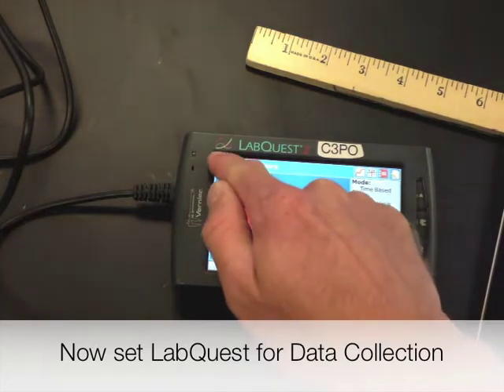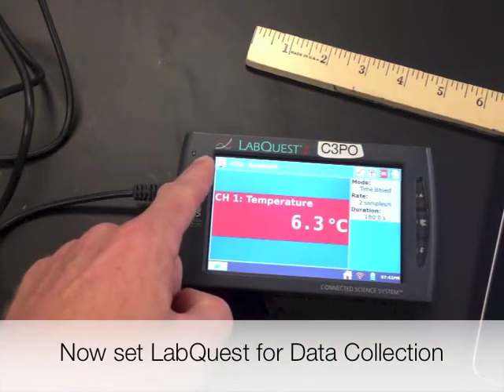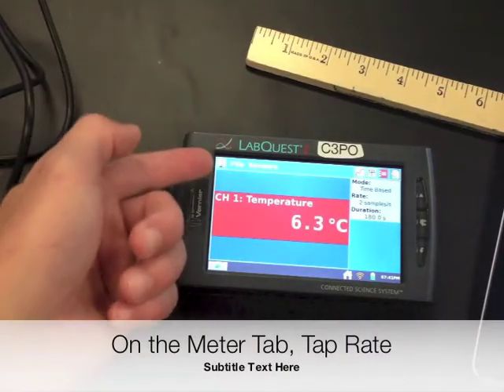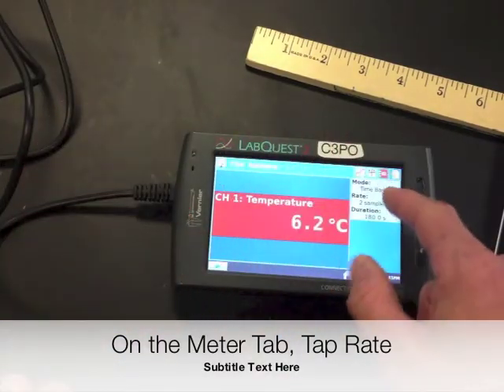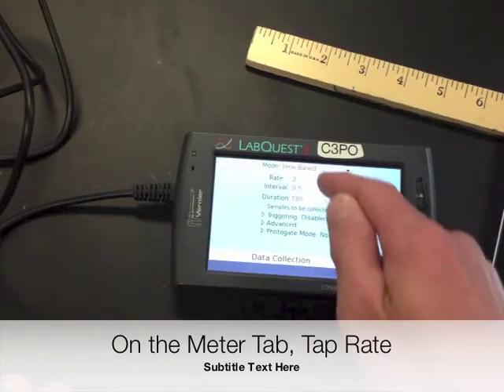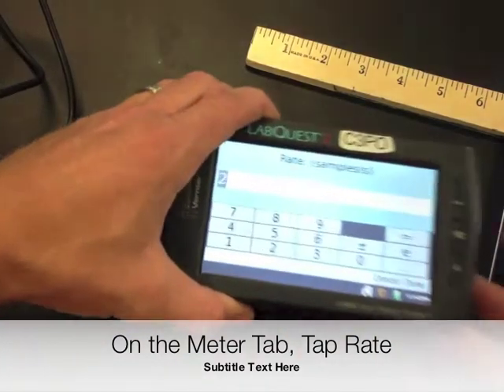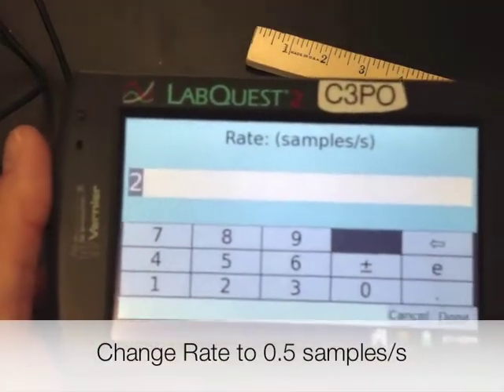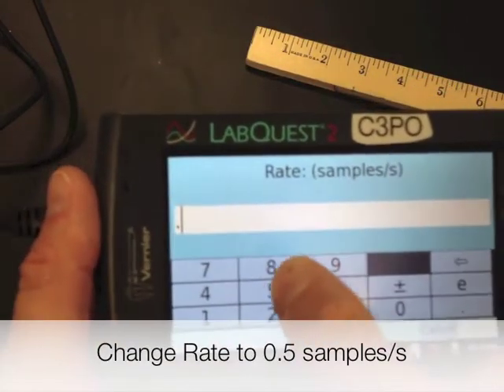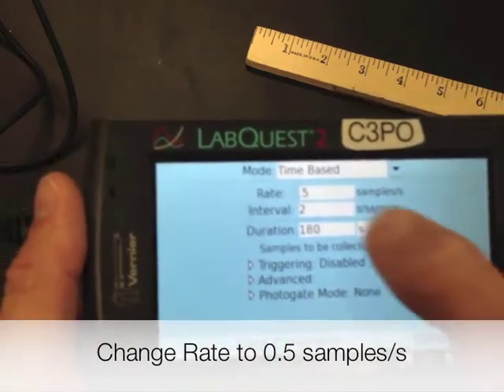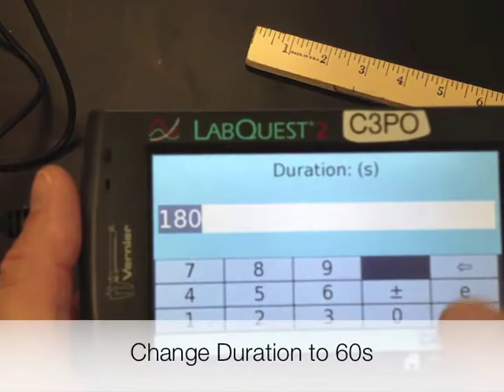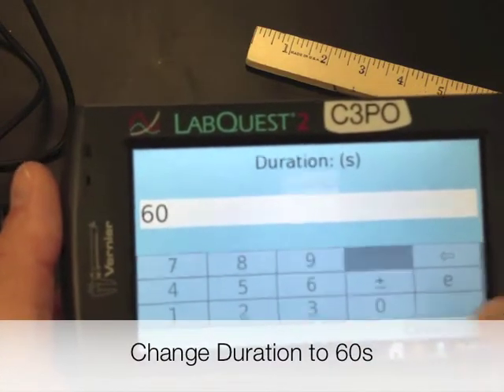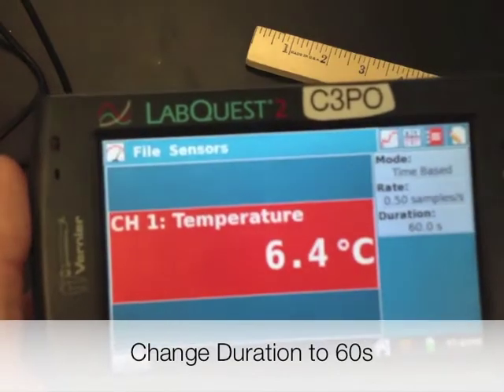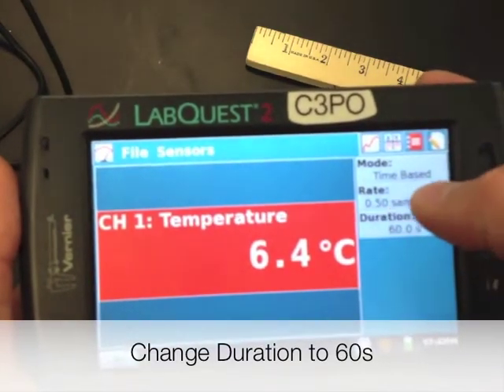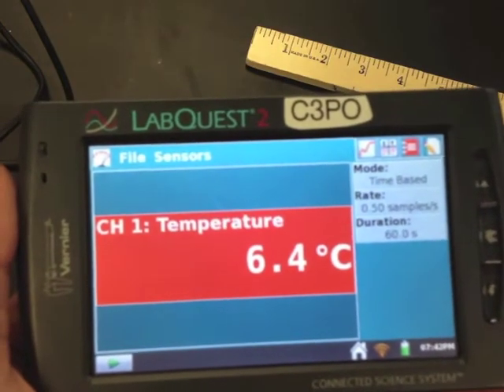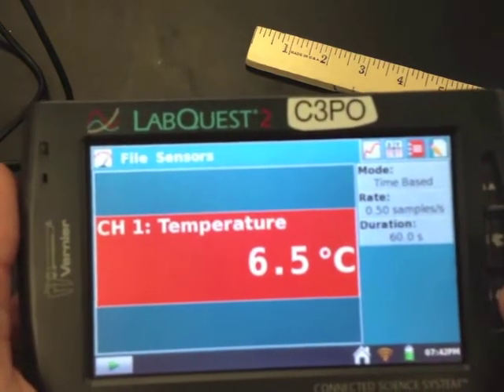On this screen, which is the meter tab, which is this icon up in the upper left, looks like how fast you're going in a car, a speedometer. You're going to tap the rate on the right, and the rate is going to be changed. Let me move this closer so you can see. The rate in samples per second is going to be 0.5. So do that. The duration, or time that you're going to collect data, is going to be 60 seconds, not 180. Okay? So now we have the rate as 0.5 samples per second, which really means that you're going to take a sample every 2 seconds. And the duration is going to go for 60 seconds.